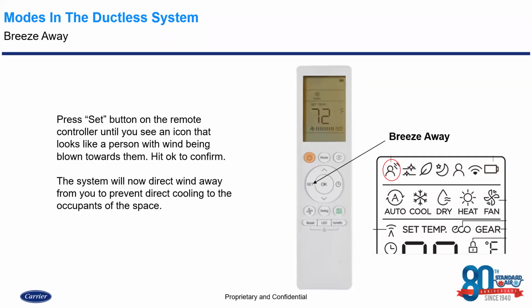And what it's going to do is now allow that system to direct that wind away from you, to prevent overcooling the occupants of the space by having that cold air blown on them, so it's a much more even comfort. Now, some people like that air blowing on them. And again, this is one of those modes that's not going to be for everybody, but something to certainly inform the customer of and also recommend based on what you know about your customer.